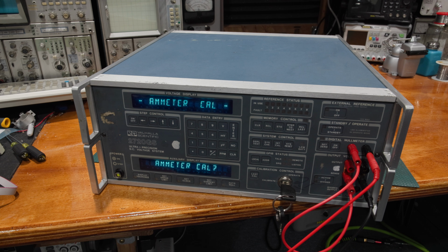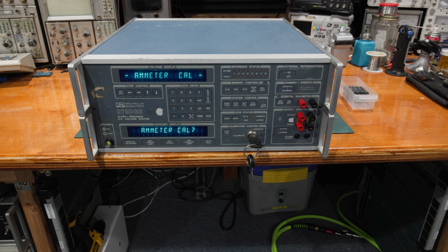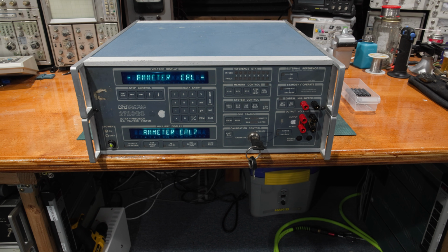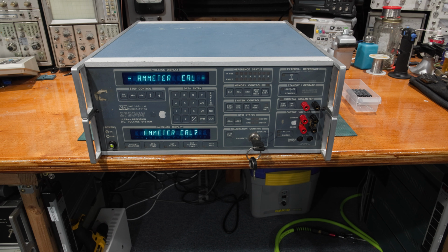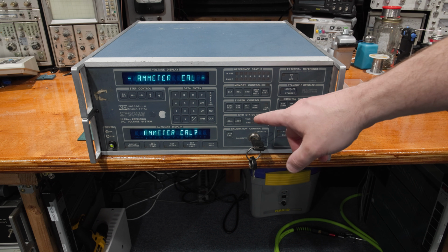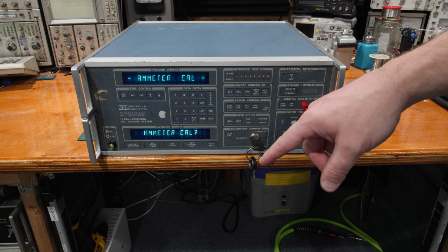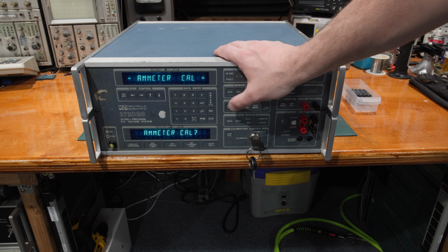Okay, for the ammeter calibration, I'm going to need a 100 ohm resistor of high precision. So let me see if I can find one of those. Okay, we're not going to do the ammeter calibration just yet. I've got to wait for the 7510 to warm up. We're not going to do drift analysis, so we're going to say no here, but we can come back to it by starting the cal process, saying no to all the voltages, and just doing the ammeter.